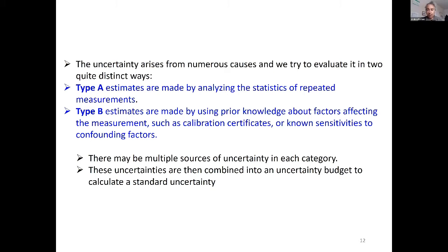uncertainties. Type A are estimated and then evaluated through statistics. Okay, you repeat measurements and you get a statistic, you get a distribution. It can be rectangular, it can be normal distribution, and you get your standard deviation of the same, possibly the same measurement. Because if during your measurement, the measurement changes, well, we are no more making statistics on the same thing. You have to take into account this. Don't put statistical analysis on something that is drifting, for example, or on a sample of snow that is melting in your hand when you weigh it.